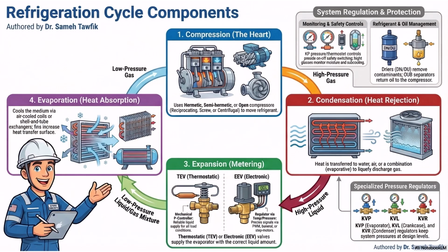Its only job is to be a heat dump. Right. It takes the heat absorbed from the cargo hold, plus the extra heat generated by the compressor's electric motor, and transfers it completely out of the system. But wait, if the goal is just to cool the gas down, why not just point a massive fan at the pipes? Why involve complex water pumps and evaporators like the diagrams in the notes show? That's a fair question. The reason is that air alone is terribly inefficient at absorbing heat quickly, especially on the scale of a commercial ship. It's just not dense enough. Exactly. You need something with more thermal mass.